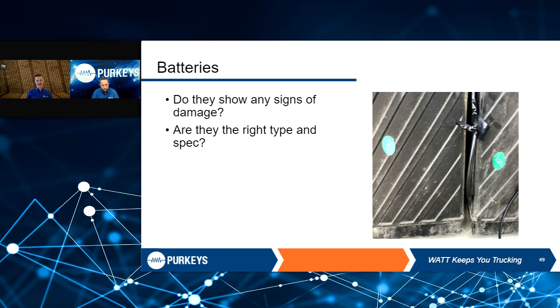Another very obvious one is any damage to the batteries themselves. This is likely caused from poor battery mounting, an issue with the battery hold down, or just poor handling of the battery while it's going in and out of that battery box. It could have been a service call in the dead of night somewhere - they dropped the battery while trying to put it in, and it's damaged. If you have a battery casing that's damaged, even if it's a brand new battery, that battery needs to be retired. That's not going to be a good thing to have inside of that battery box.